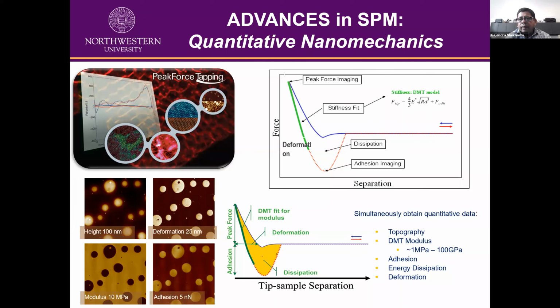A lot of users are using it, and this is especially popular for monitoring cell dynamics in real time. All living cells are dynamic, changing shapes due to the rearrangement of their cytoskeleton scaffold, and spreading and migrating on the cell culture substrates. These processes and the mechanical changes that accompany them can be monitored with peak force, because the forces between the tip and sample are in the pico-Newton range, as compared to nanonewtons in the tapping mode. So you are exerting a pretty low force on the sample, which allows you to measure the mechanical properties of the biological samples.